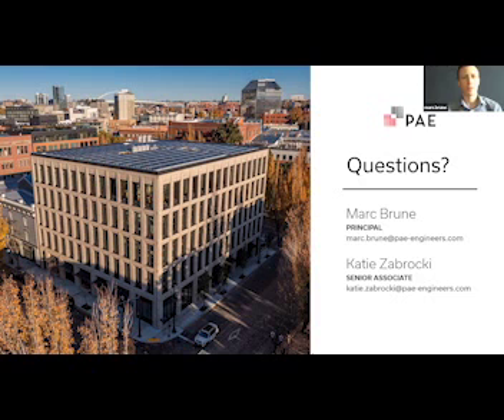Did you have anything to add? Yeah, pretty similar - the Candida building has a radiant floor just like ours, and like Katie said, we watch dew point and reset based on that. We have kind of a belt and suspenders approach - we look for condensation, and as a secondary measure, if that happens we'd more quickly reset the temperature. So it hasn't been an issue down there - it's been running for a couple of years now.